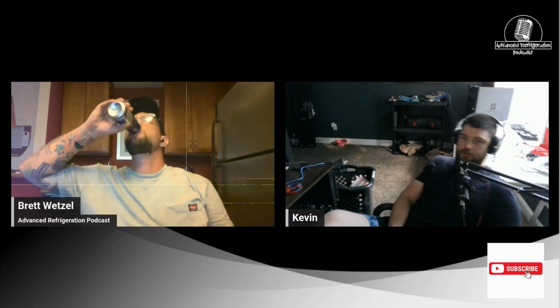That's why I was going to FAFO. I was just going to play around with it and try it, because I've never tried this before. It would be cool at full fan speed if you could say there's a differential meter on here and it says plugged condenser. I would think at full fan speed, it would be the only one that matters. Because, hey, I'm at full fan speed, head pressure still climbing, differential's high. Get somebody out here to clean this damn condenser before it trips. They'll show up after it trips.